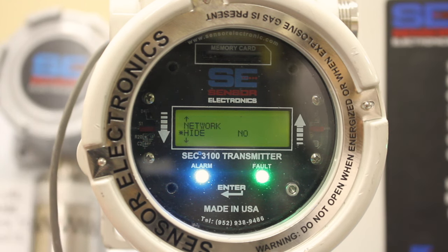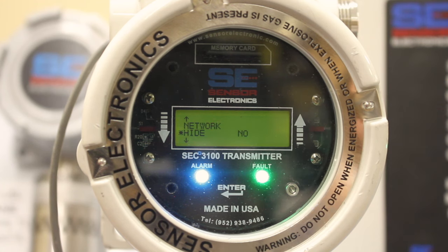Next one is a menu called hide. What that does is it hides the readings all the way up to the low alarm set point. So it would just show 0% LEL until it reached 11%, and then it would actually start reading. It's a feature that is really not used very much. Self-test. This allows you to actually test the sensor.